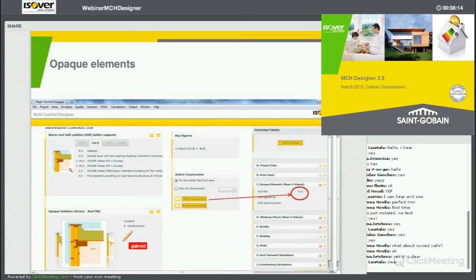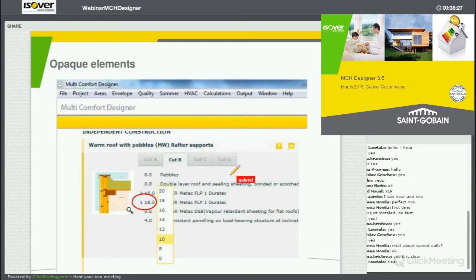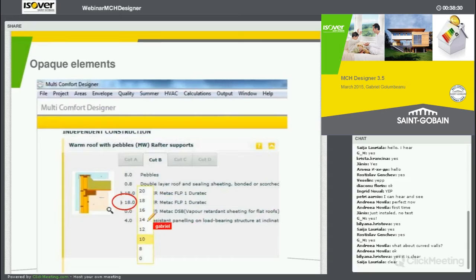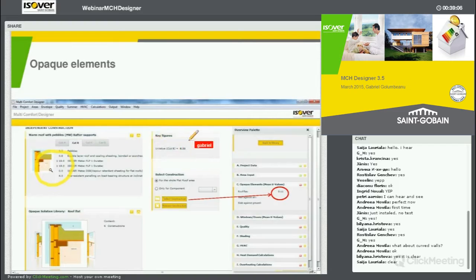This allows me to play a little bit with the construction details that I would like to use. I can scroll to the left or to the right, and I have different types of construction. Here you can see there are two options for changing the characteristics of this detail. There is an option to play with whatever the detail was defined as — a thickness of 18 — but you also have the possibility of selecting different thicknesses. By selecting different thicknesses, you are playing around with the U-values or with the thermal performance of the wall. The thermal performance is specified here — in this case it is 0.11.